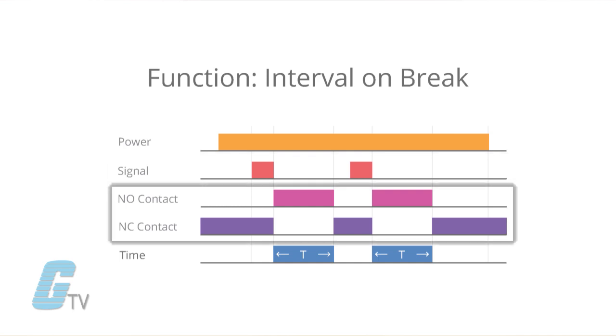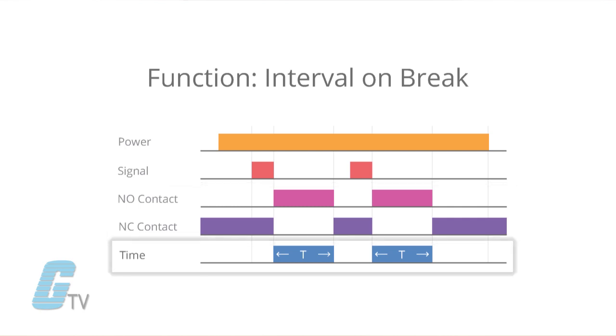The next one or two lines depending on the diagram indicates the relay's contact state. Some diagrams will show the open as well as the closed state of the contacts. Sometimes the timing function is seen on its own line, but may also have a separate place marker to show when the timer begins and ends in relation to the contact state.